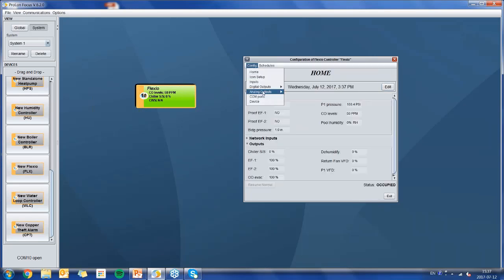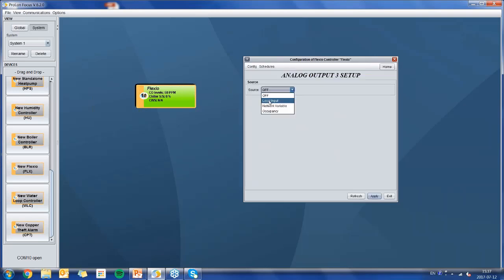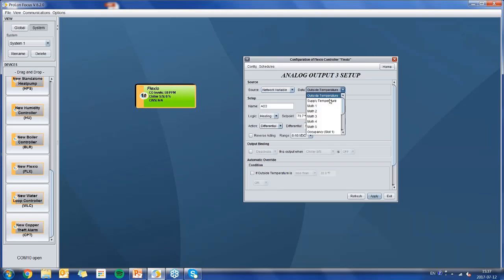If I go back to this, I think this is the last available output that I had. So far I've been basically making it go off the local input every time. I can also choose a network variable. Here we have all the network variables: outside temperature, supply temperature, our 5 math functions, and our 8 occupancy slots, which I'll get into in just a moment. I could drive something simply based on outside air temperature, or based on occupancy, whatever you want, we can do that. So I'll just talk about occupancy and so on.